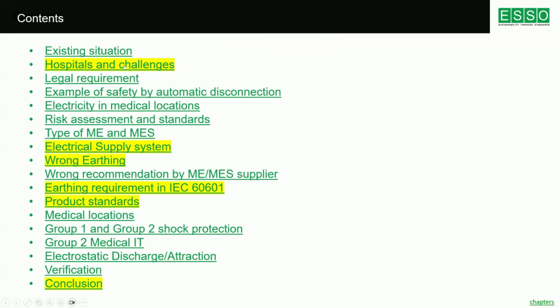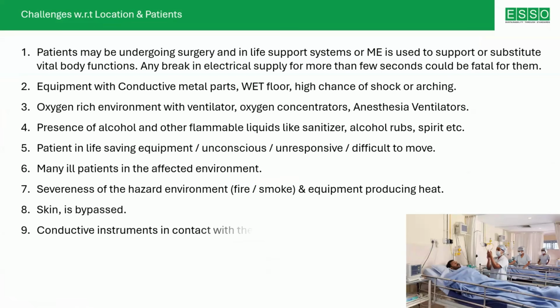Coming to the subject, last week we discussed various subjects such as the challenges we have in the hospital with respect to the electrical subject, but I will quickly go through it. This was explained in the last webinar. The challenge here is that patients may be undergoing surgery and may be on life-saving equipment, so any disconnection of supply will be a disaster. So continuity of supply is very much essential. Even if we have generators, multiple UPS, multiple transformers with automatic or manual changeover, sometimes continuity of supply cannot be ensured if there is a fault. During a fault, continuity of supply must be ensured because all the medical electrical equipment are capable of working under single fault condition, or they are able to ensure safety under single fault condition.